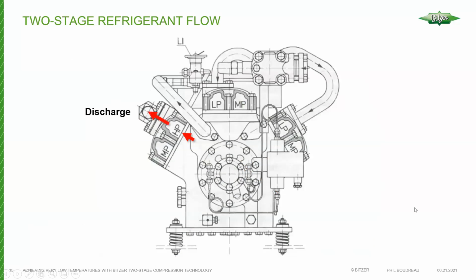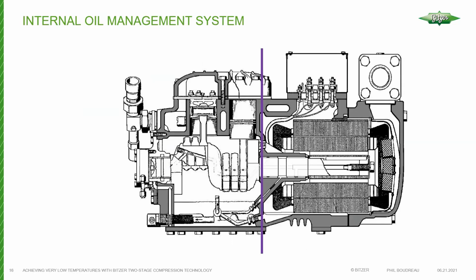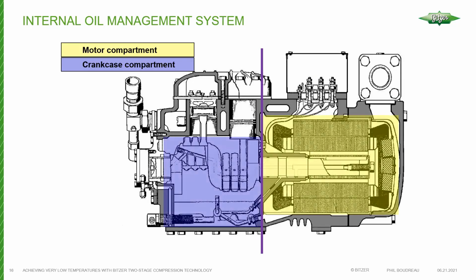So the final stage would be, again, the refrigerant, after it absorbed the heat from the motor, now it enters the final stage of compression and then off to the discharge. Inside the compressor, we have a partition that separates your motor compartment from the compressor or the crankcase compartment. And the crankcase, of course, is where your oil is. So they're separated. Suction gas comes in, as I mentioned, we cool the motor.